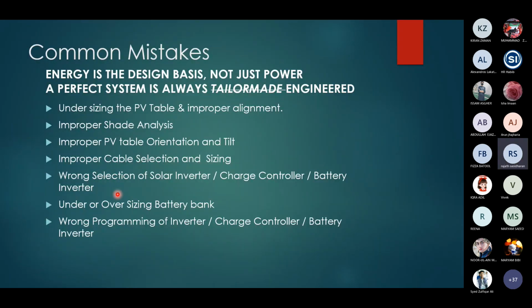You have to calculate the ampacity of a cable, I'm sure you're all qualified engineers to do that, since wrong selection of cable is a problem. Please remember, DC cables and AC cables are two different types of cables in terms of construction, so you should not use AC twisted pair cables from the market for a DC application. You can create a fire hazard or underperformance.